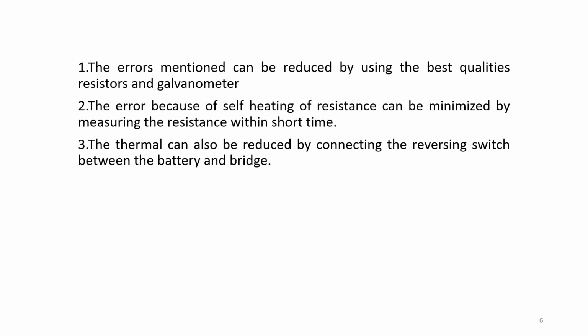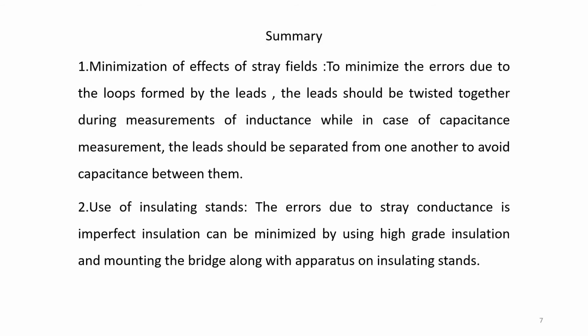The errors mentioned can be reduced by using the best quality resistors and galvanometers. Next, the error because of self-heating of resistance can be minimized by measuring the resistance within a short time. The thermal EMF can also be reduced by connecting the reversing switch between the battery and the bridge.